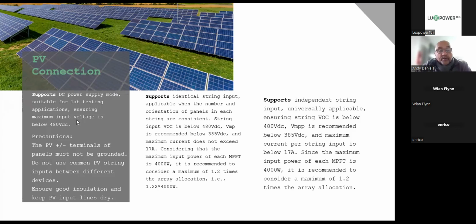Don't use that when you're doing PV, because with PV, we have to select one of the two tracking profiles. One is either parallel strings, and we're going to go through that in a second, or independent strings. And the MPPT, for those of you who don't know, stands for maximum power point tracking. So the logic on there always allows it to track the maximum power point. We can have identical string inputs, or we can have independent string inputs. Now remember that we've got three criteria that we have to meet, and you cannot exceed any one of them in any circumstance.